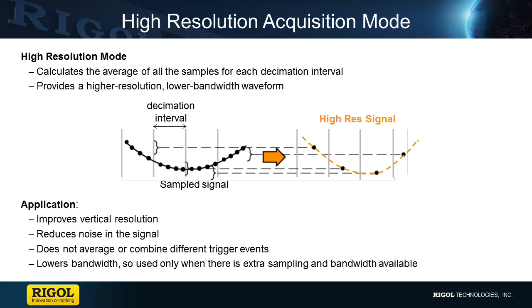The most common technique is a high resolution acquisition mode. This is accomplished by averaging samples that are between points in the display to improve accuracy and reduce noise on the display.